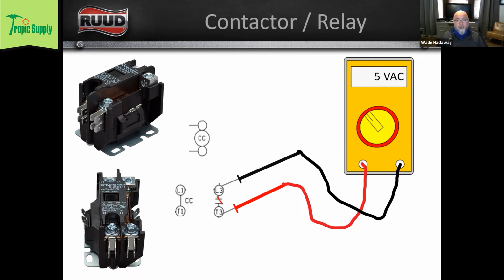Now, some much bigger contactors that can handle much larger loads and are more expensive, like motor starters and stuff like that, have rebuildable contacts and linkages. Your typical contactor for a residential piece of equipment does not. Wade, is there a standard voltage drop that indicates replacement of the contactor? So you really shouldn't see any voltage drop there.